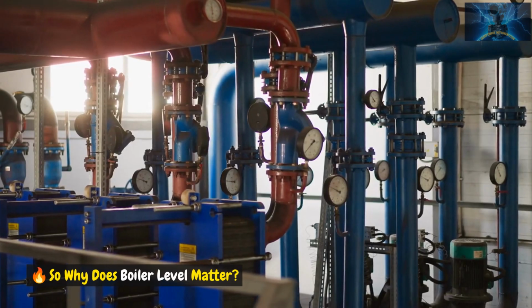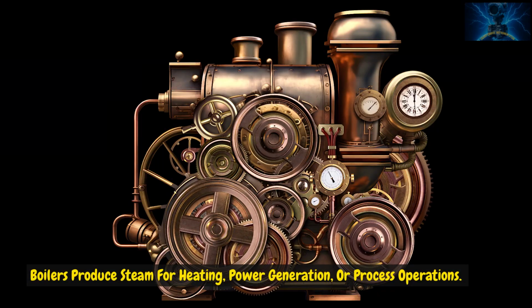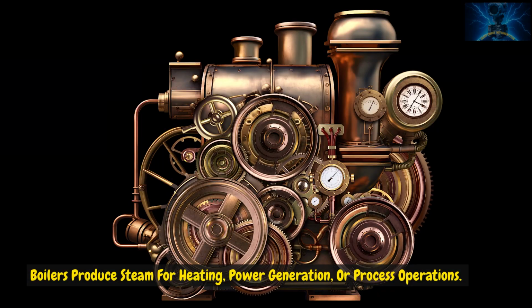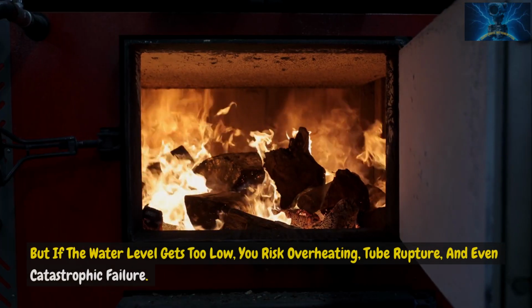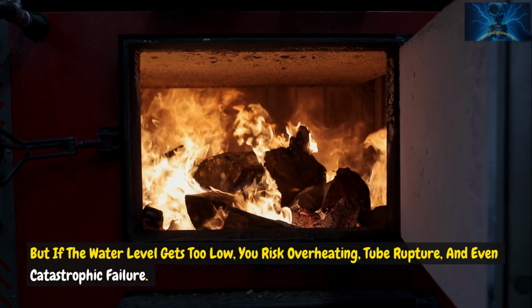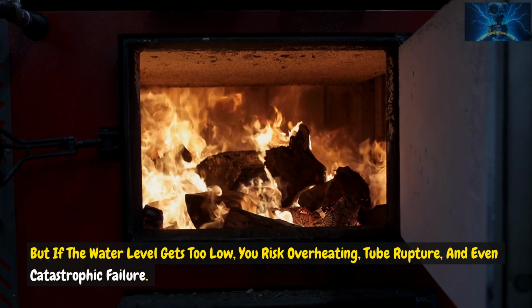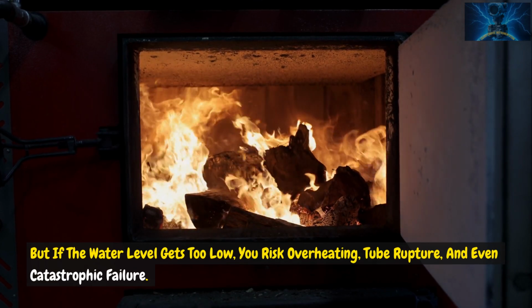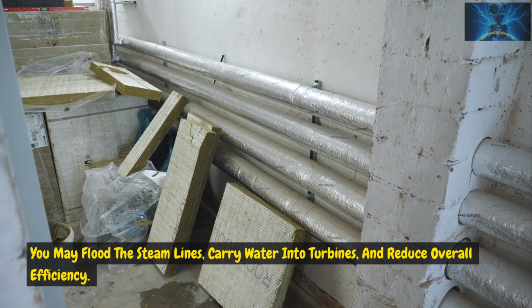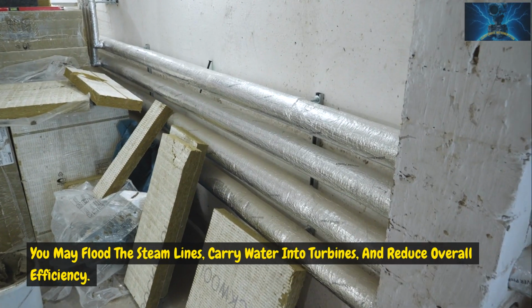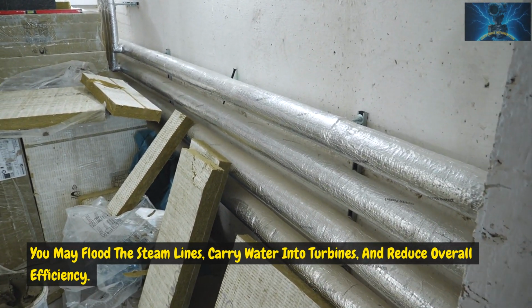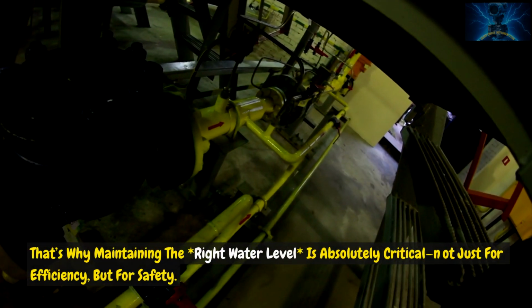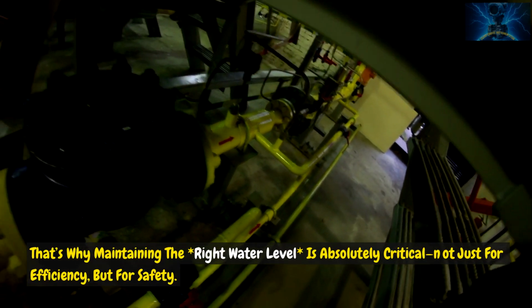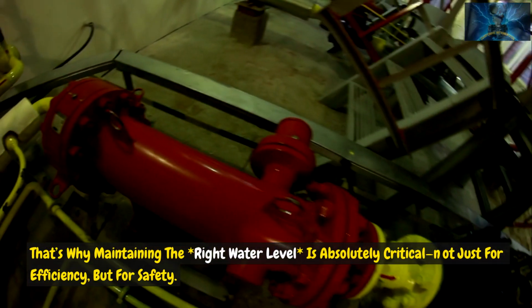So why does boiler level matter? Boilers produce steam for heating, power generation, or process operations. But if the water level gets too low, you risk overheating, tube rupture, and even catastrophic failure. Too high? You may flood the steam lines, carry water into turbines, and reduce overall efficiency. That's why maintaining the right water level is absolutely critical, not just for efficiency, but for safety.